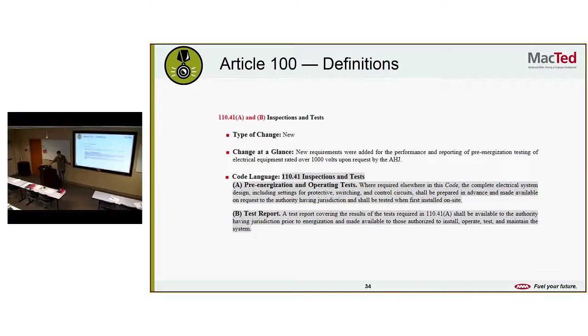Inspections and tests. New requirements were added for the performance and reporting of pre-energization testing of electrical equipment rated over 1,000 volts. So if you have stuff that's over 1,000 volts, they want it tested before you put power to it. Sounds like a good idea. Where required elsewhere in the code, the complete electrical system design, including settings for protective switching and control circuits, shall be prepared in advance and made available on request to the AHJ, and shall be tested when first installed on site. Is anybody in our company doing anything with 1,000 volt power?